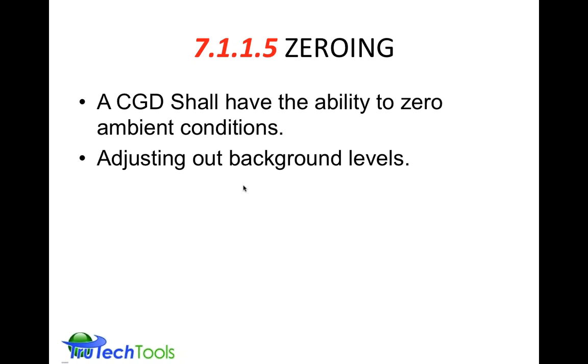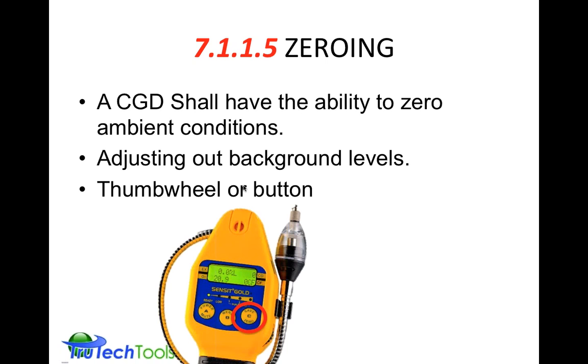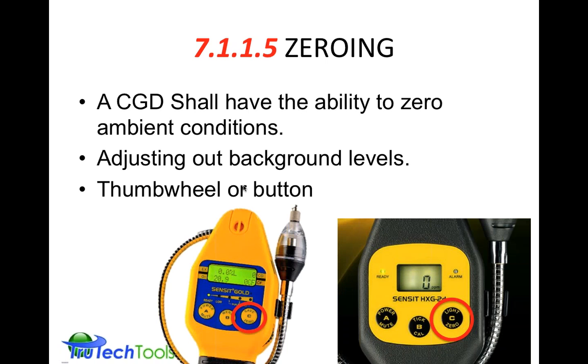You must be able to zero out the ambient conditions with your combustible gas detector by adjusting out background levels, using a thumb wheel or a button. In the case of the two products we looked at before, there is a zeroing button which allows you to adjust out those background levels. So again, this helps in the gas leak detection mode.